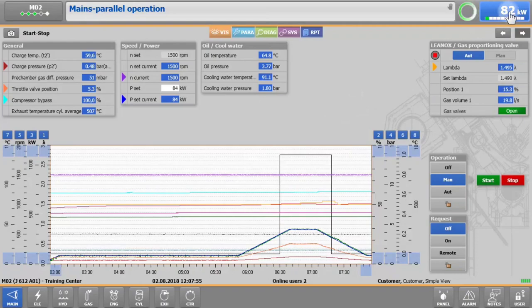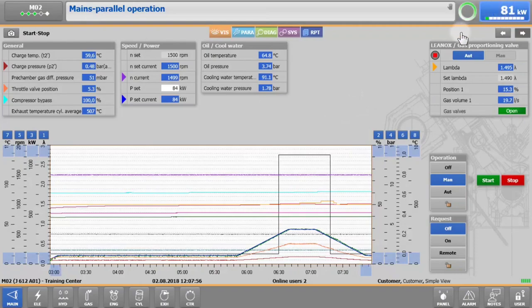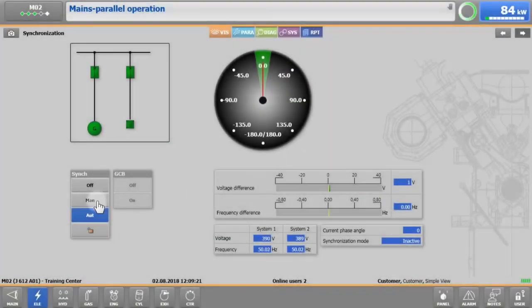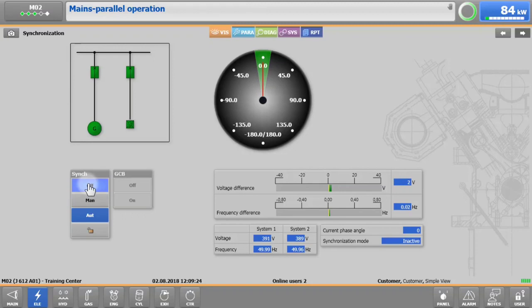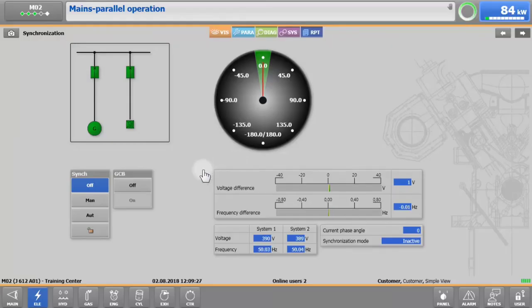When 10% has been reached, change the sync switch from auto to off, then open the generator circuit breaker manually by tapping on GCB off.